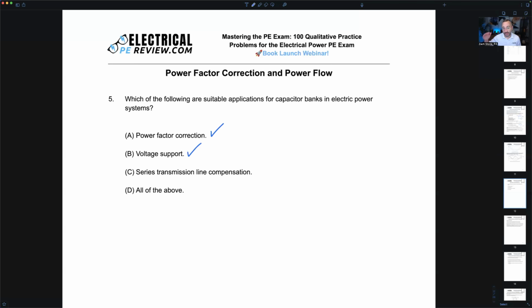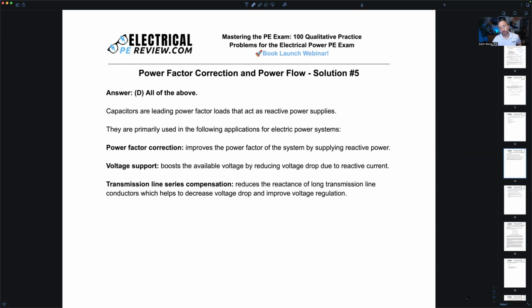What happens when I decrease the overall impedance as current flows through it? Now we're back to talking about decreasing voltage drop again. When we decrease voltage drop, what happens? We've got more voltage available at our load. So series transmission line compensation is also an application for capacitor banks, which makes the answer to this problem D, all of the above. All right, on the next page, I've got a summary. This is the solution that's provided in the book.